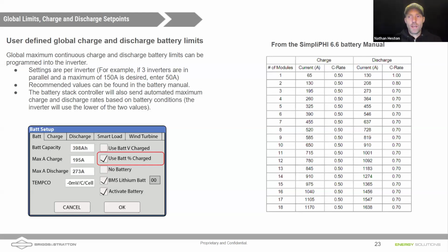One more thing I want to point out is that these charge and discharge limits that we see, 195 amps, Daniel, is that AC or DC? That's DC. I wish Sol-Ark would add a little DC there. Yeah, that's DC amperage. So we're talking about DC amperage for a 48-volt battery. Typically the charging cycle is happening at about 52 to 56 volts. So that's amps DC. Keep that in mind.